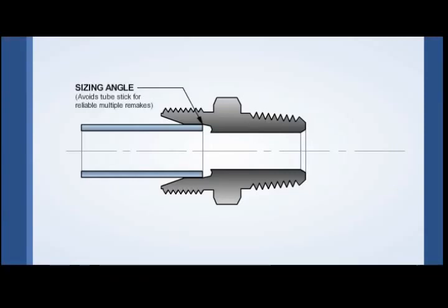During assembly, the sizing angle gently guides the tube slightly inwards, helping to prevent tube stick. Avoiding tube stick allows for multiple fitting remakes. In fact, if assembled and reassembled properly, Gyrolok fittings can be remade more than 100 times and still be demonstrated to be leak-tight.